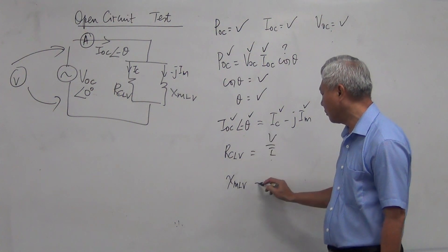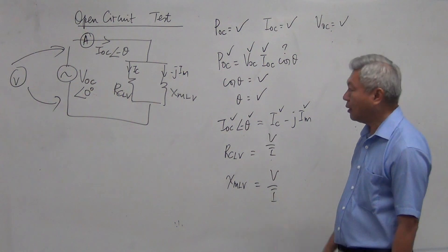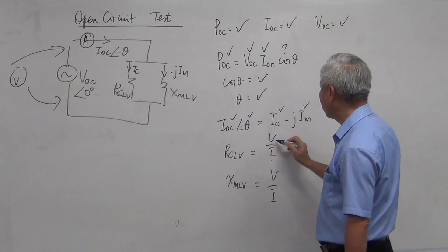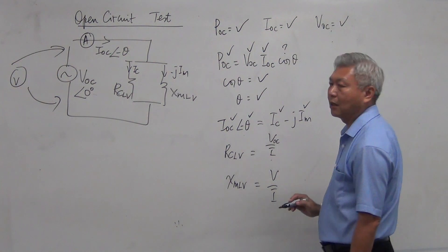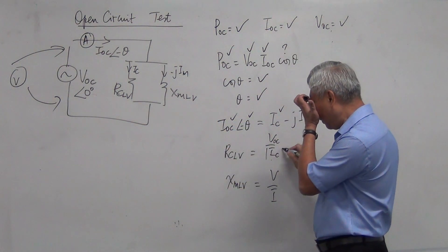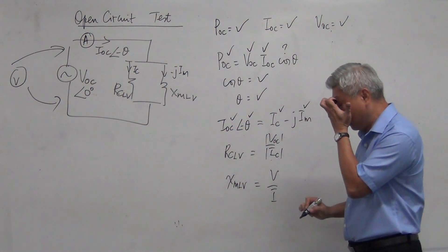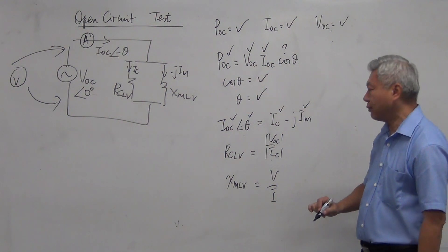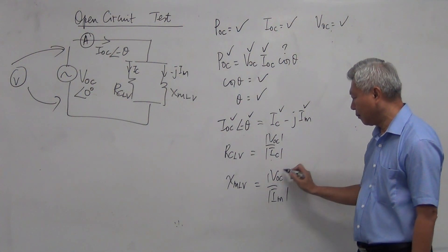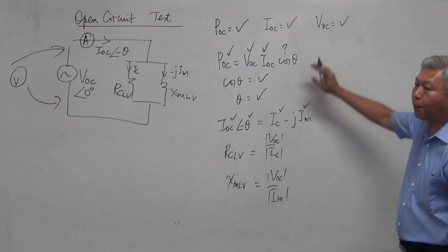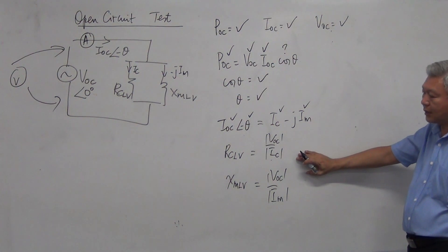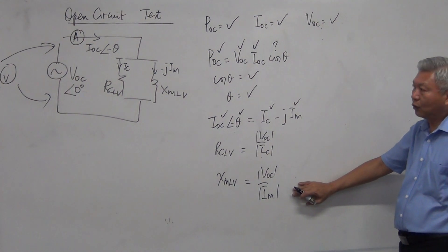Then, using Ohm's law to find RC and XM: since this is a parallel circuit with voltage VOC across both branches, RC equals VOC divided by IC, and XM equals VOC divided by IM. We only talk about the magnitude. That is the open circuit test — the method to derive the core loss resistance and magnetizing reactance at the low voltage side.